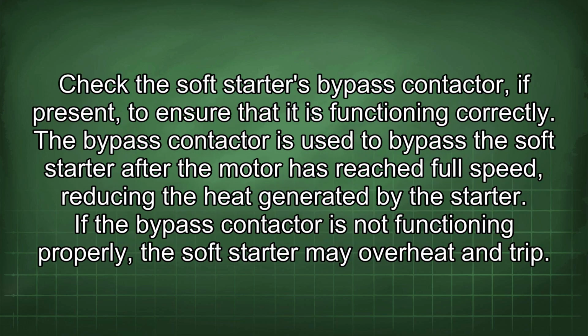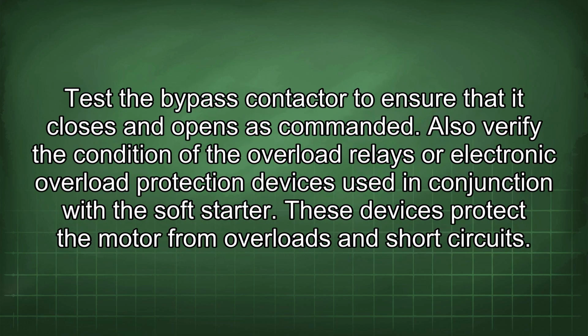Check the soft starter's bypass contactor, if present, to ensure that it is functioning correctly. The bypass contactor is used to bypass the soft starter after the motor has reached full speed, reducing the heat generated by the starter. If the bypass contactor is not functioning properly, the soft starter may overheat and trip. Test the bypass contactor to ensure that it closes and opens as commanded.